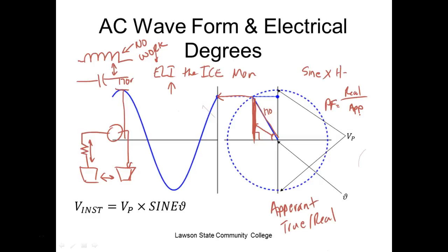And we call it a start capacitor. What's the function of those things? It is to create a phase shift so that single phase motor will start. Now normally we kick that start winding out because once something's in motion, it creates its own phase shift, right? Does that make sense? But we do have different motors. We have what they call a capacitive run motor. And you'll look at those, they'll have two capacitors on them, or they'll have one capacitor that's got three leads on it. Those motors create more run horsepower using a smaller size.